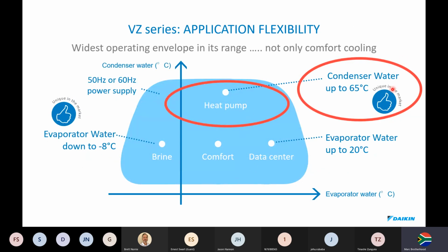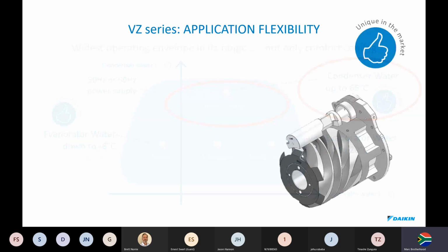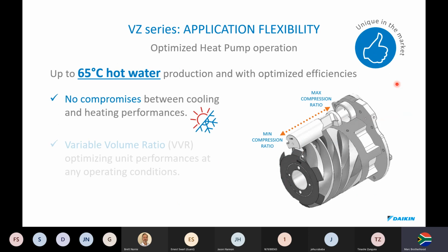Now we move on to heat pumps. If you want hot water out of our inverter chillers, up to 65-degree hot water production with optimized efficiencies. So there's no compromises between heating and cooling heat pump performance. We do this through this mechanical device, which monitors pressure ratio differentials with pressure sensors. They in turn create a voltage, which is going to drive a little solenoid, and this solenoid is going to advance or retard hydraulically the slide to optimize the compression ratio on the volume between high and low side.